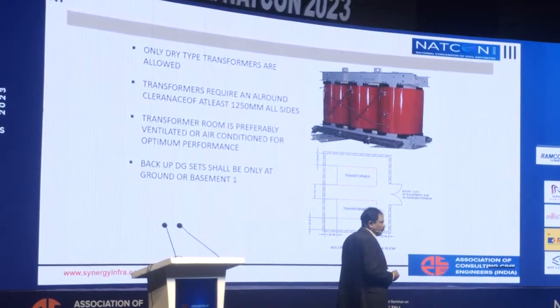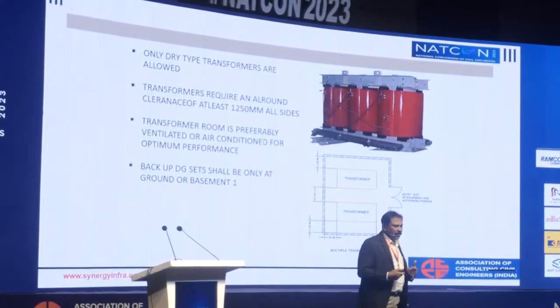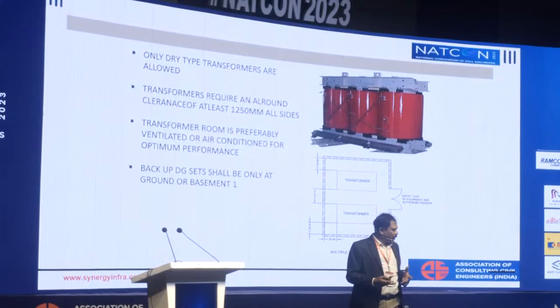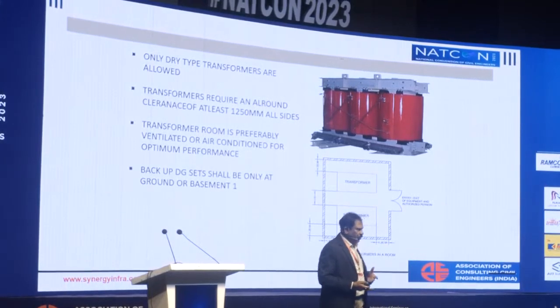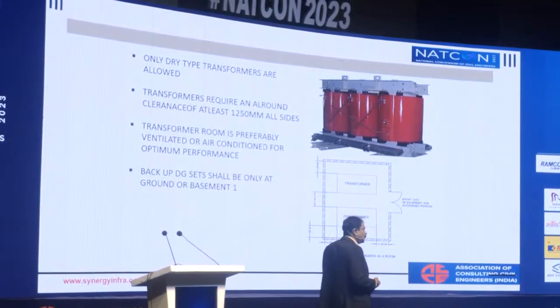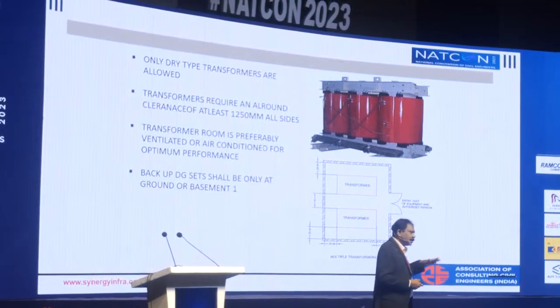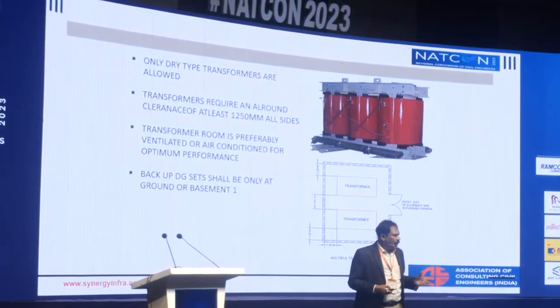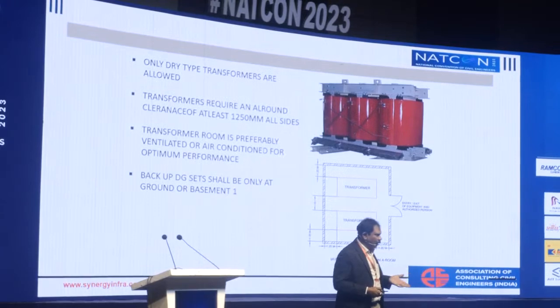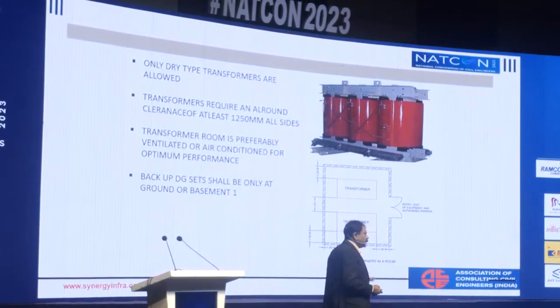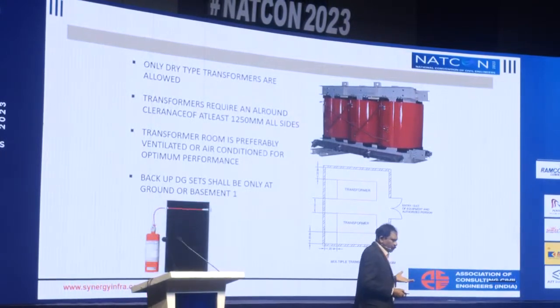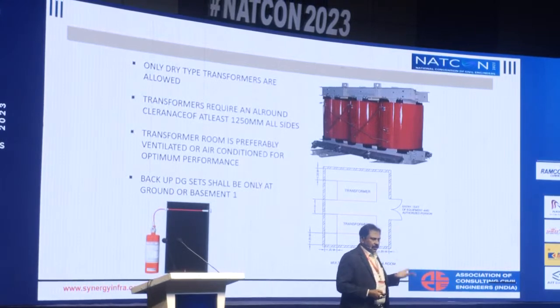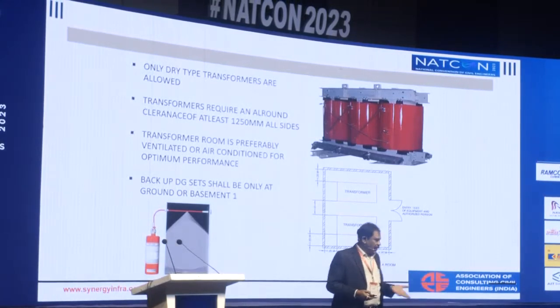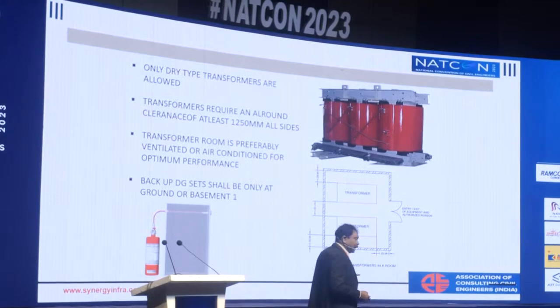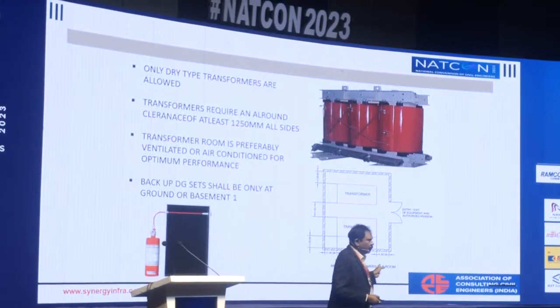Only thing is the backup power. Because in India we depend heavily on the backup power because of power interruptions and quality of power issues and other things. That is the reason you need to have backup. But these backup DG sets have to be at the ground level or at the basement level. There is no alternative to that. We can't take the DG sets to any higher level. So naturally they have to be 11 kV DG sets.